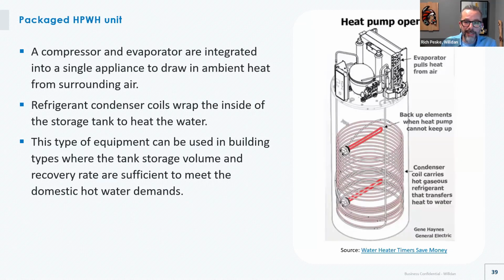What kinds are there? First, the integrated heat pump water heater, shown in the diagram here. It looks like the water heater you might have in your house or in a closet. It's simple and compact, all in one, with the heat pump and tank combined into a single appliance. It pulls heat from the nearby air and transfers it directly into the water in the same unit. This is ideal for settings where space is tight, like smaller homes, apartments, or utility closets. The compact nature makes it easier to install and less intrusive than other options, and with everything housed together, you avoid the complexity of running separate refrigerant lines and installing multiple components.